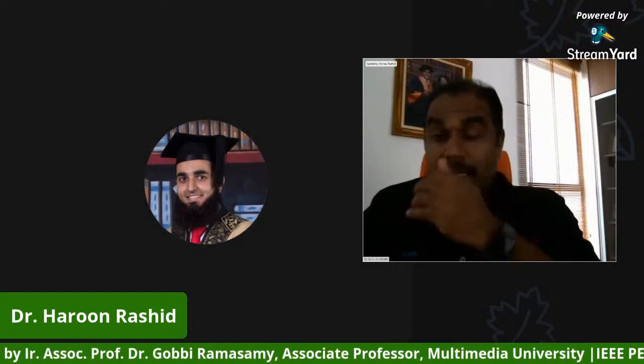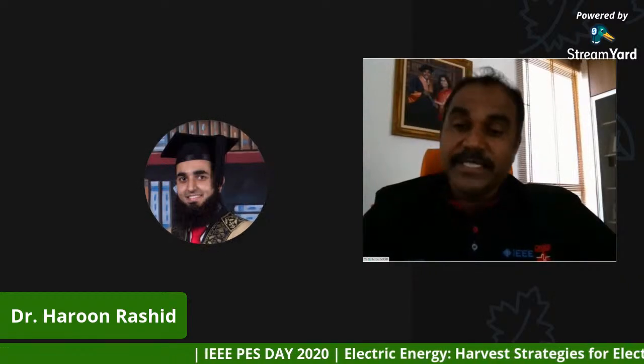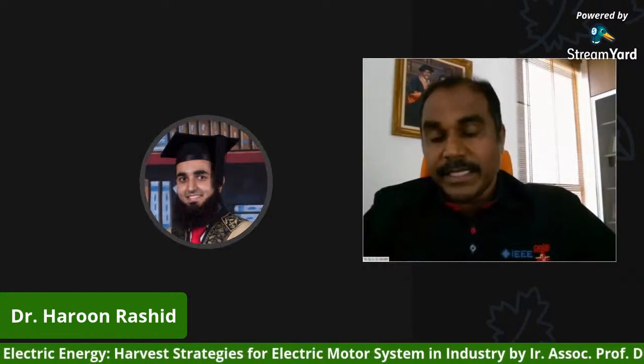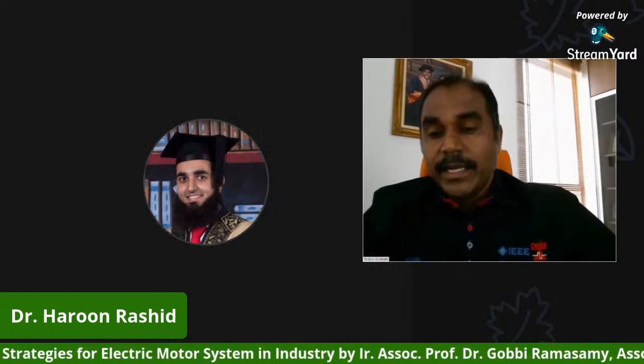Generally, what happens is we expect the motor to operate at at least 75%. That is the optimum. At 75% usually you get the best efficiency. So we always encourage people to go for 75%. Yes, if it goes higher, it's fine.